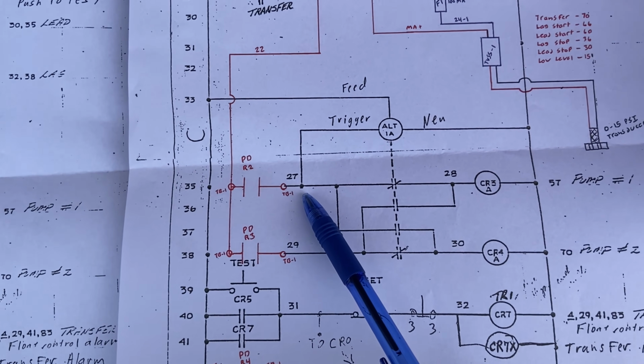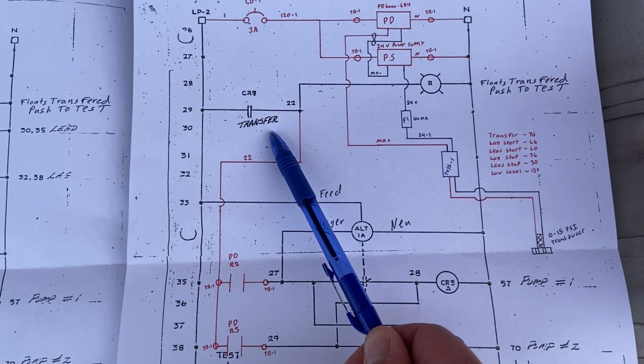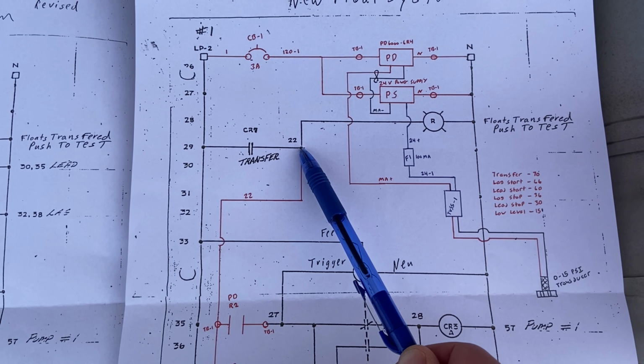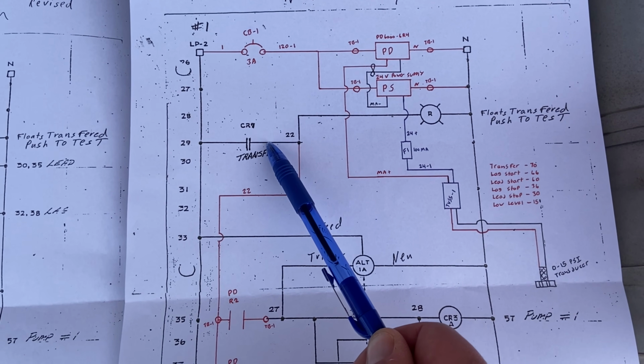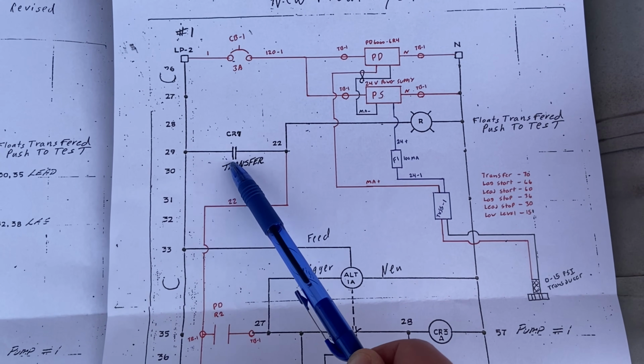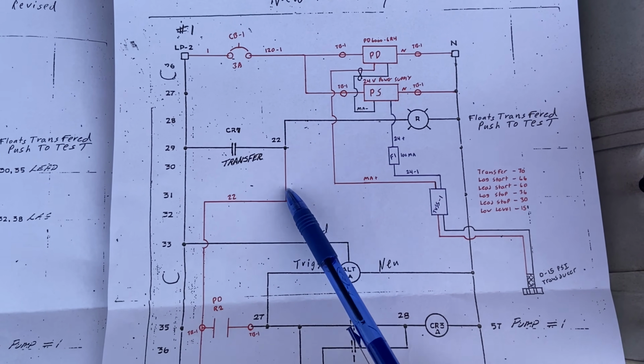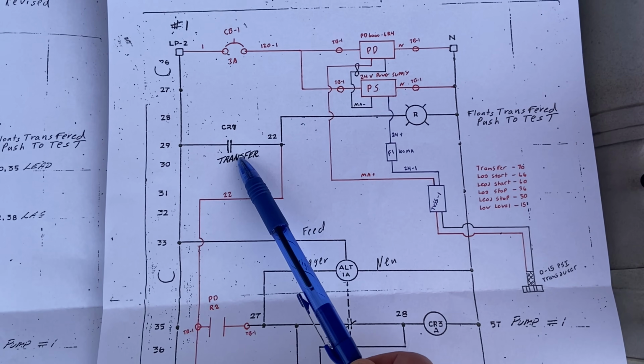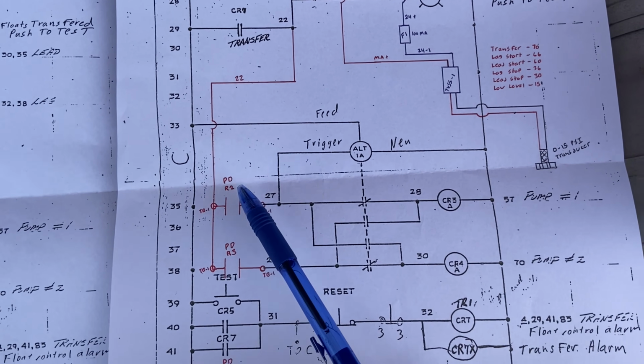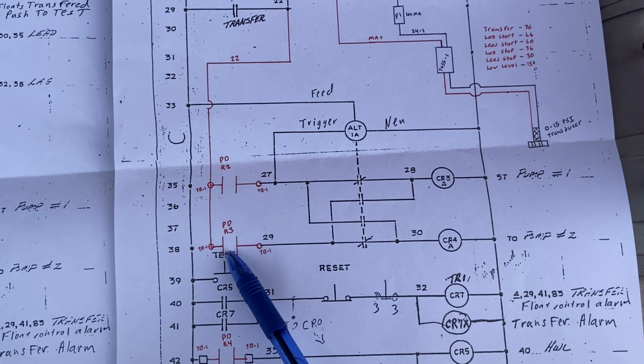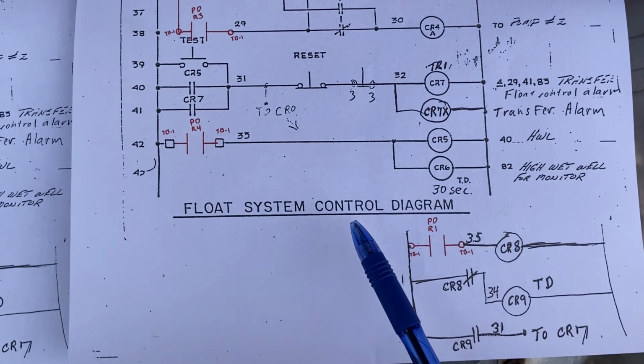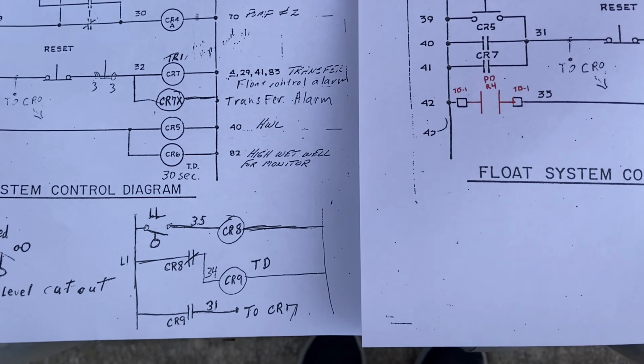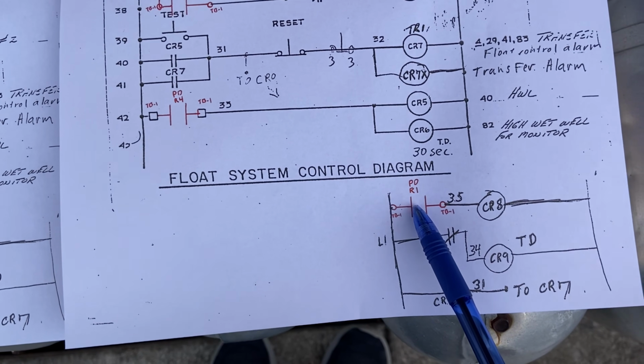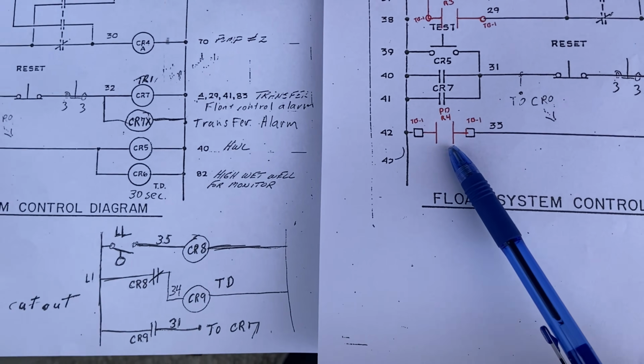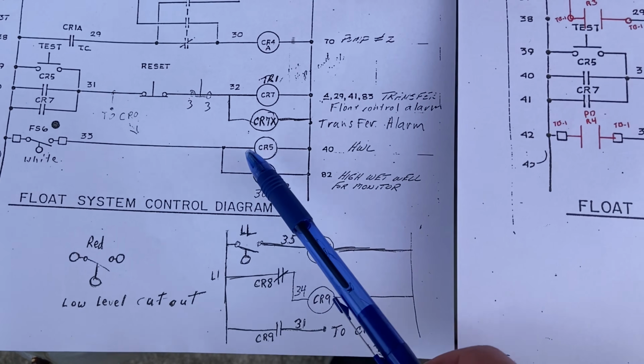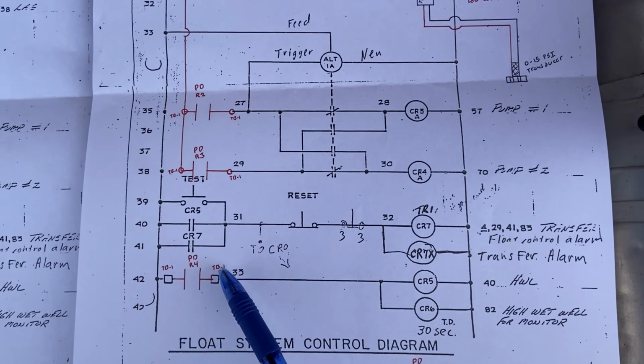We also changed what wire fed those 2 relays because we don't want to give them constant power. We came off of this wire 22, which is part of the secondary circuit. It comes off that transfer relay, which latches in when you transfer to secondary. We don't want to give it constant power because then the 2 systems would conflict with each other. So you got to make sure you use the right part of the circuit. So from there, it just goes into our alternator, business as usual. And then we have our other 2 contacts, our low level contact and our transfer contact, which, as I said before, pretty straightforward, just replacing 1 float with 1 relay.